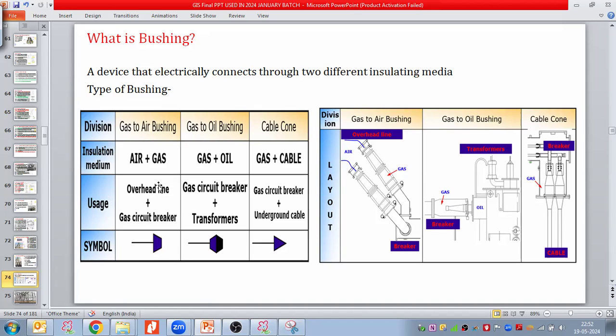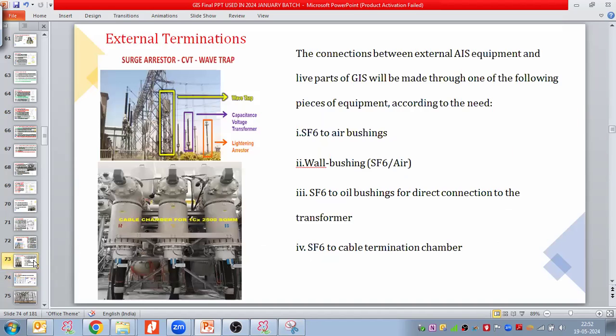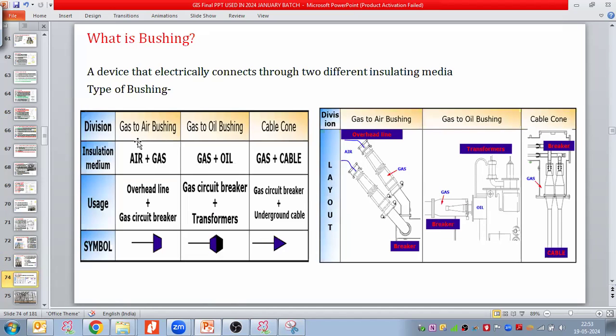So we need to understand about the bushing symbol as well. Gas to air bushing: if I'm taking SF6 to air bushings, or gas to air bushings, in that case it looks like this. This is a type of bushing. It is connecting the overhead line plus the gas breaker or gas equipment, and this symbol we use for that reason when we are taking the connection here.